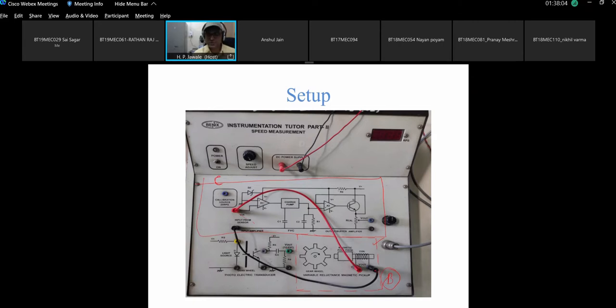Now what it is showing, the coil that is given with some electrical current is going to generate a magnetic flux. When this comes in front of the material, the reluctance, that is a back EMF produced, will be something different than when this recess comes in front of the pickup, and then the difference will give the pulse. Number of pulse per unit time is counted and then it's correlated with the speed. Any doubt in understanding the setup?